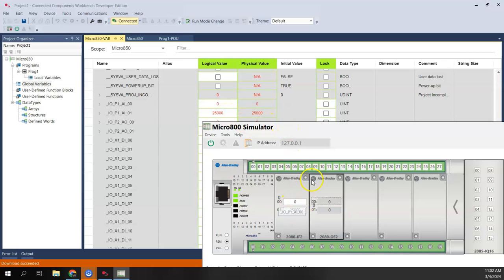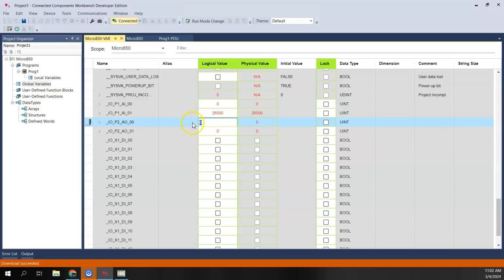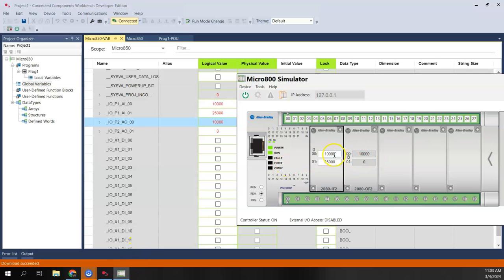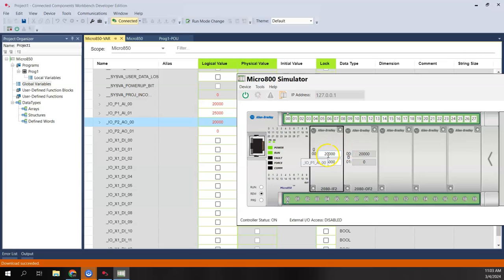I can type in a value to go right into my controller program to simulate. For the analog output, if I type in 10000, that value shows up in the tag — and it also went into the analog input because the analog output is wired back into the analog input via virtual wire. If I change that number to 20000, it comes back here showing 20000. So virtual wire connection means the analog output can feed back into an analog input for simulation.